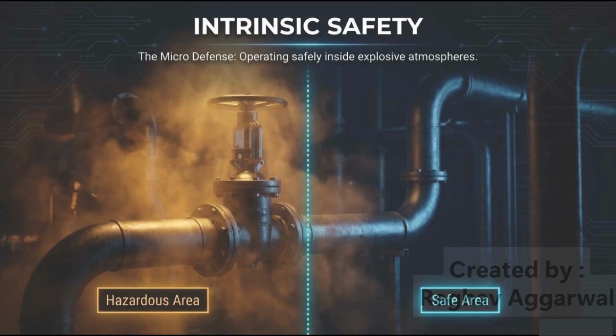The final protection philosophy in this training is intrinsic safety. Intrinsic safety focuses on environments where flammable gases, vapors, or other explosive atmospheres may be present. There may be a condition that a safe area is connected to a hazardous area. Equipment located in the hazardous area must be designed so that it cannot release enough electrical energy to ignite an explosive atmosphere. Unlike other protection methods that manage large amounts of energy, intrinsic safety works at the micro level.